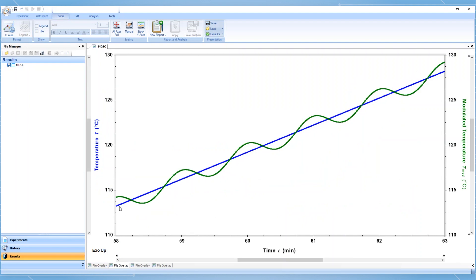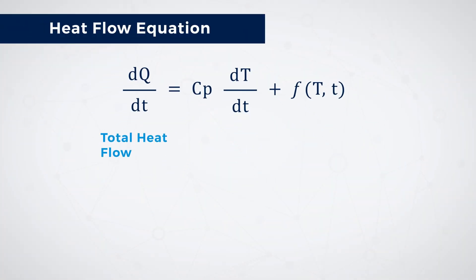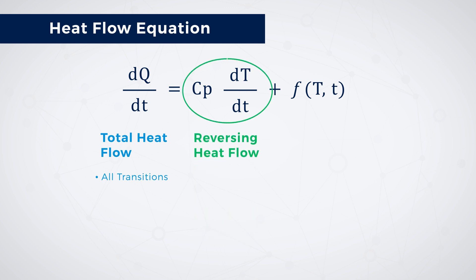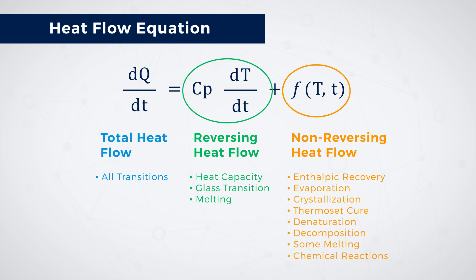By controlling the instantaneous heating rate in this way, MDSC separates out which component of the total heat flow is able to follow the temperature modulation. This component is referred to as the reversing heat flow. The reversing heat flow component is a function of the sample's intrinsic heat capacity and the rate of temperature change. The other part of the heat flow equation is a function of absolute temperature and time — the kinetic component. This term does not follow modulation and is the non-reversing heat flow. It is important to remember that reversing and non-reversing heat flow signals are not necessarily a measure of reversible and irreversible transitions.